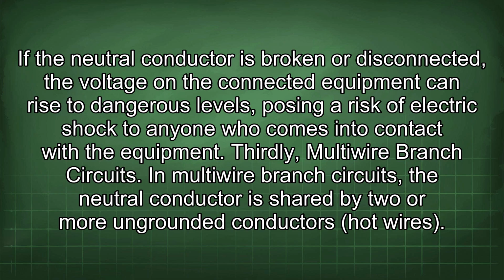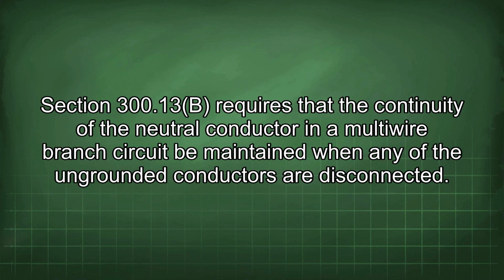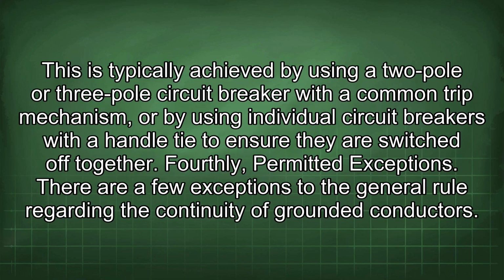Thirdly, multiwire branch circuits. In multiwire branch circuits, the neutral conductor is shared by two or more ungrounded conductors, the hot wires. Section 300.13b requires that the continuity of the neutral conductor in a multiwire branch circuit be maintained when any of the ungrounded conductors are disconnected. This is typically achieved by using a 2-pole or 3-pole circuit breaker with a common trip mechanism, or by using individual circuit breakers with the handle tie to ensure they are switched off together.